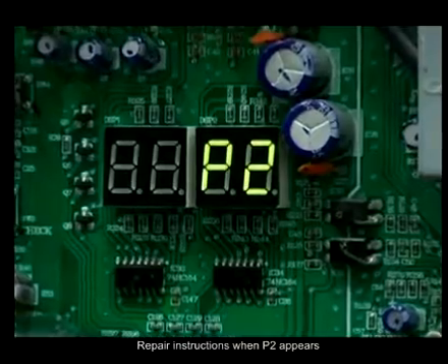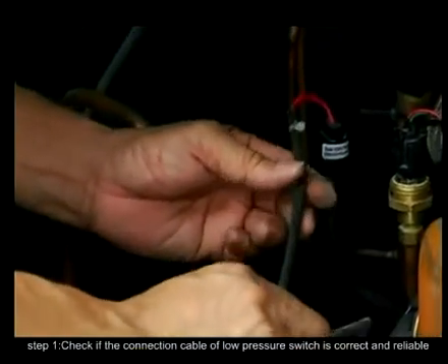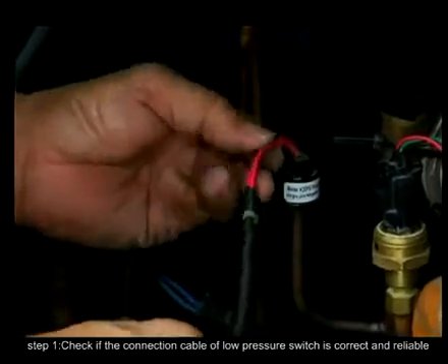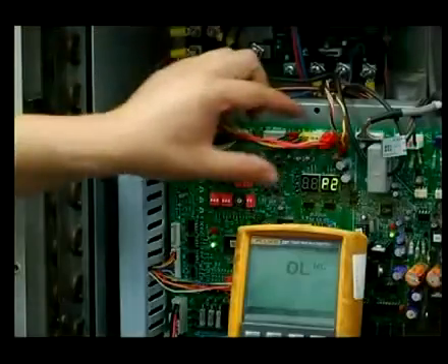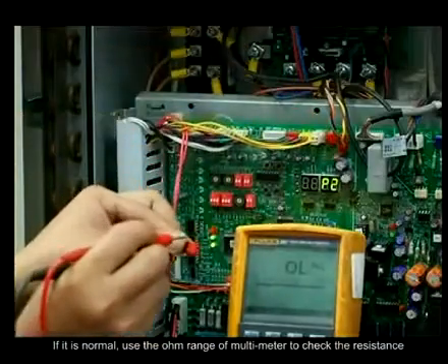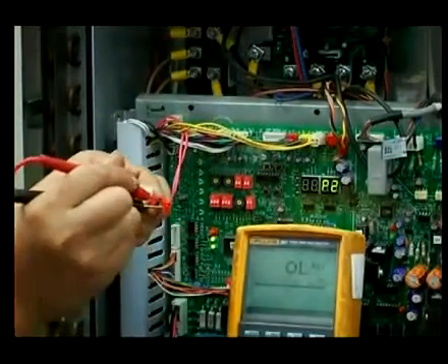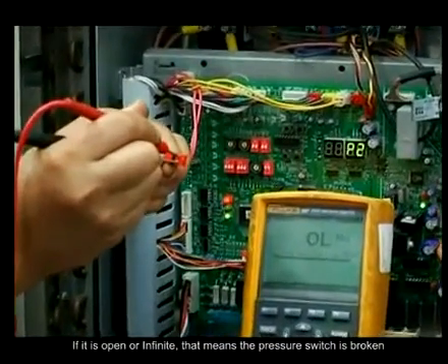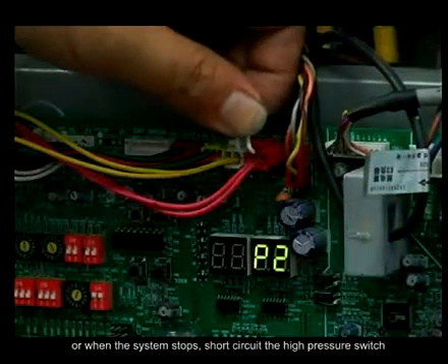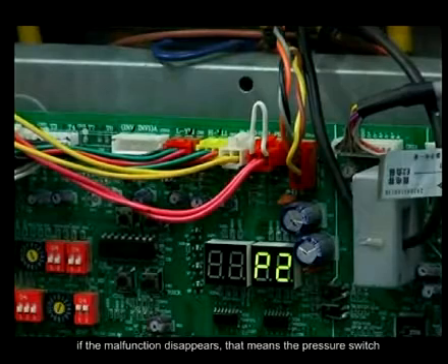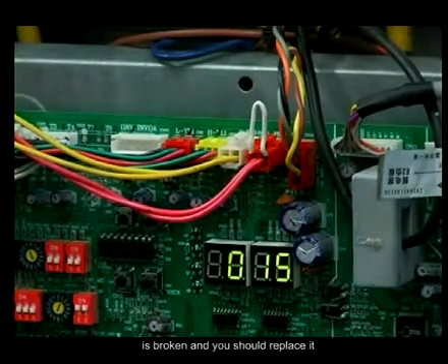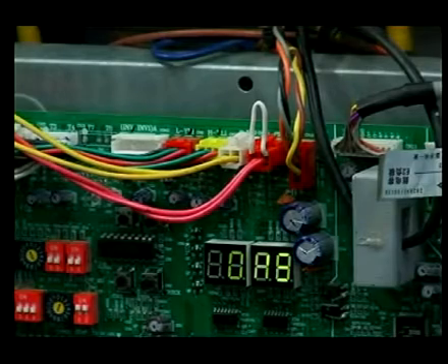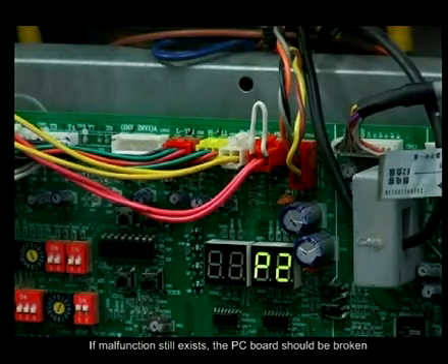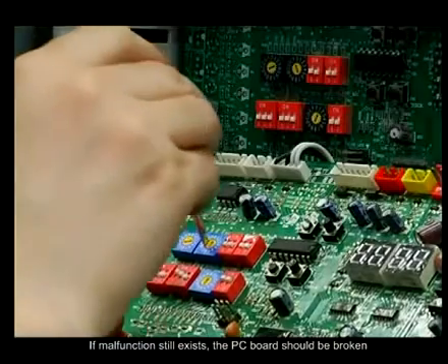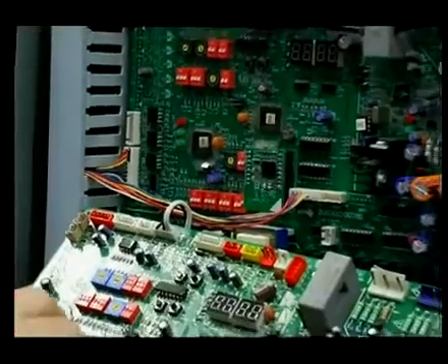Repair instructions when P2 appears. Step 1. Check if the connection cable of low pressure switch is correct and reliable. If it is normal, use the OHM range of multimeter to check the resistance. If it is open or infinite, that means the pressure switch is broken. Or, when the system stops, short-circuit the high-pressure switch. If the malfunction disappears, that means the pressure switch is broken and you should replace it. If malfunction still exists, the PC board should be broken. You have to replace a new one.